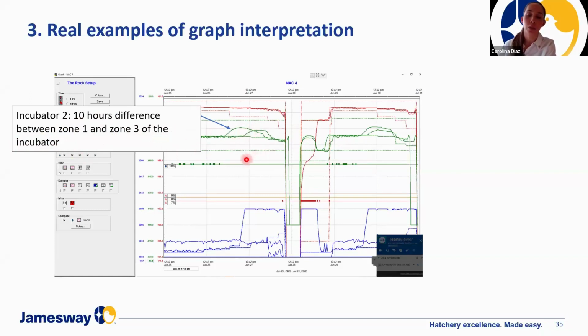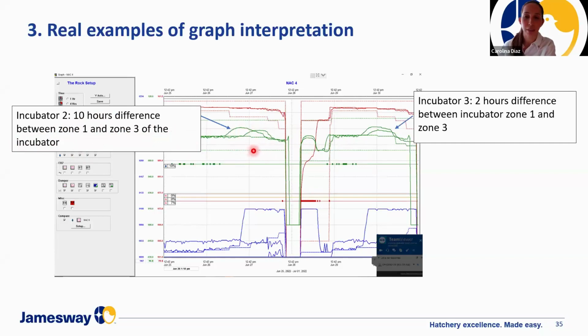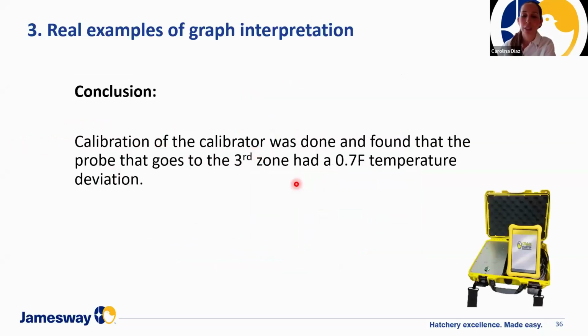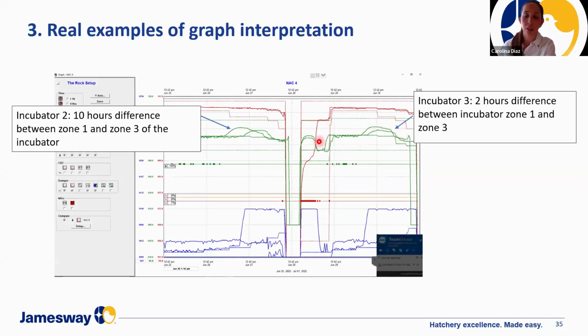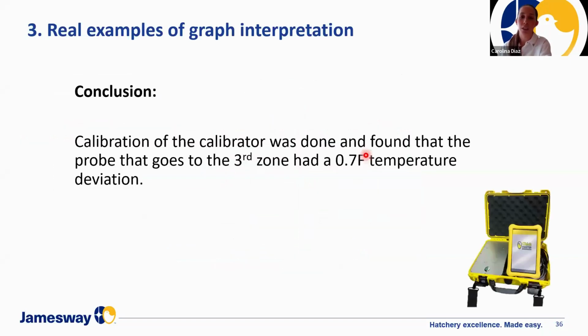So we went directly to review calibration. However, as it was a repeat case, because we see it on a very regular frequency, it was not just one machine, it was more than one machine. So we went over calibrating the calibrator. And what happened is that the probe that always went to the front zone of the machines, calibrating this front zone of the incubator, had a deviation of 0.7 Fahrenheit. So the machines that were calibrated with this calibrator were all off.